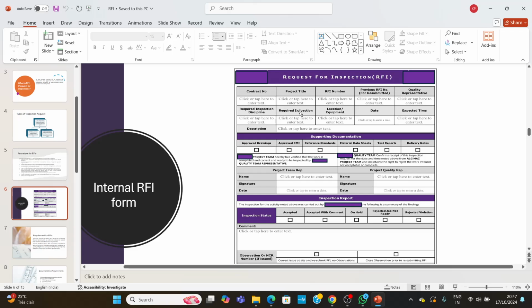The next column is required inspection. This means you have to describe the activity. For example, if the RFI is a request for inspection for insulator hoisting, you have to write the complete description: request for inspection for suspension assembly of the towers with the tower number and location. Here you also provide the location and equipment number, then in the date column, put a date and the expected time when you want to make the inspection.